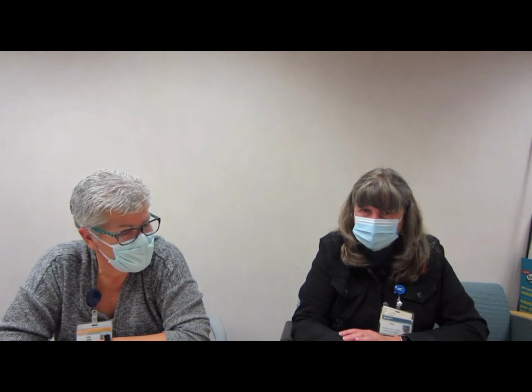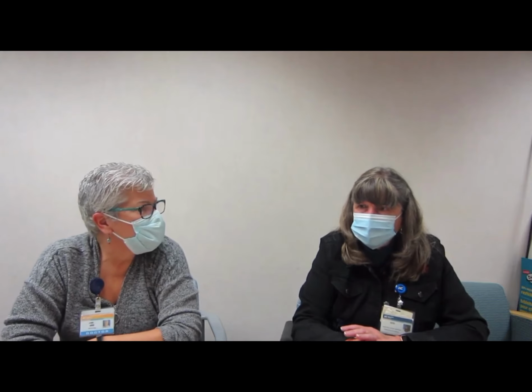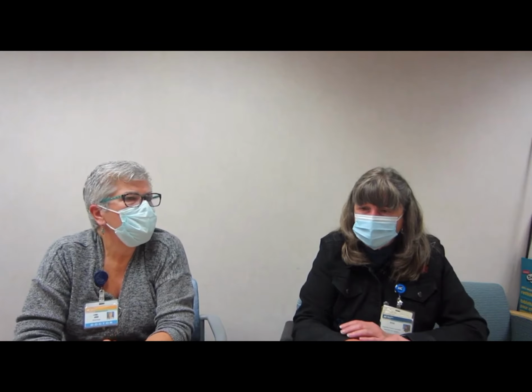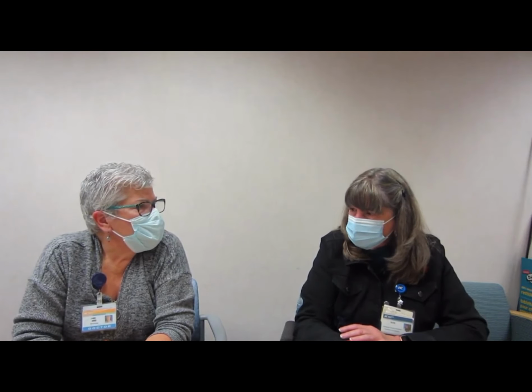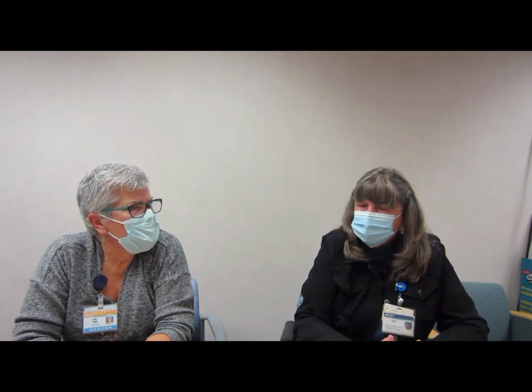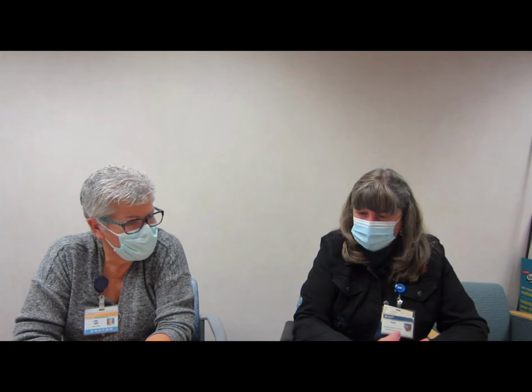We're going to have a picture that shows a little drawing of the lungs and tells you exactly what to watch for and what can cause the servo to increase or decrease. But remember that there is not a set pressure that works for any baby. It's all different depending on the baby and also depending on the settings. So if Dr. Hino comes and says she wants her baby's jet rate changed from 420 to 360, my servo is going to change. So you have to get used to that new servo before you actually see a change. With any vent change, the servo will change some.